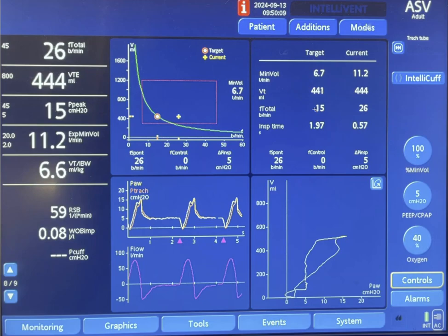Based on the RC the best or the optimal respiratory rate is determined and here you can see that machine is targeting optimal respiratory rate of 15 per minute and at the same time it determines the optimal or the target tidal volume and here it is decided that the optimal tidal volume for the patient will be around 440.